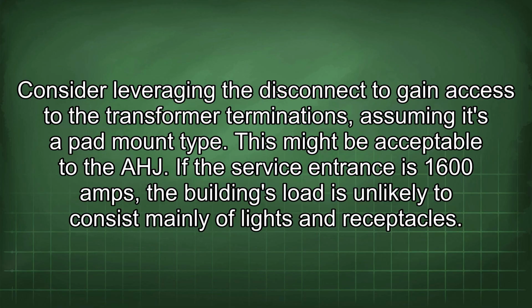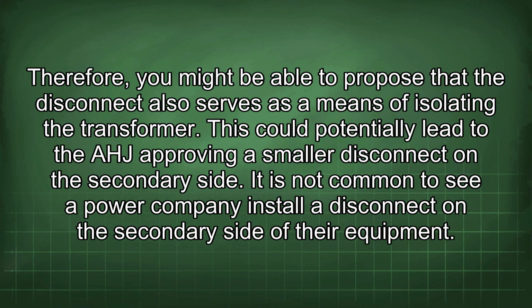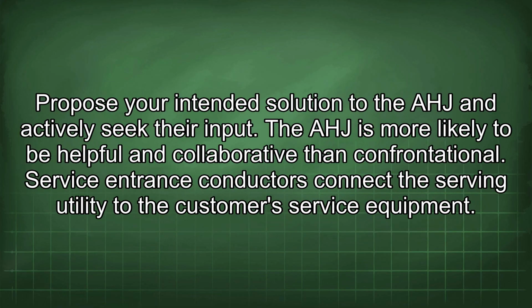If the service entrance is 1600 amps, the building's load is unlikely to consist mainly of lights and receptacles. Therefore, you might be able to propose that the disconnect also serves as a means of isolating the transformer. This could potentially lead to the AHJ approving a smaller disconnect on the secondary side. It is not common to see a power company install a disconnect on the secondary side of their equipment. Propose your intended solution to the AHJ and actively seek their input. The AHJ is more likely to be helpful and collaborative than confrontational.